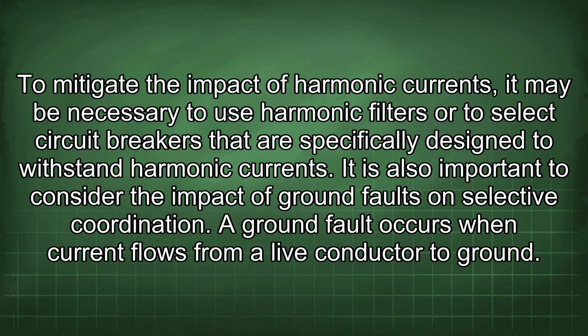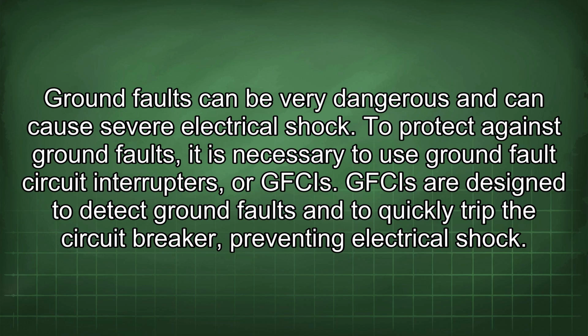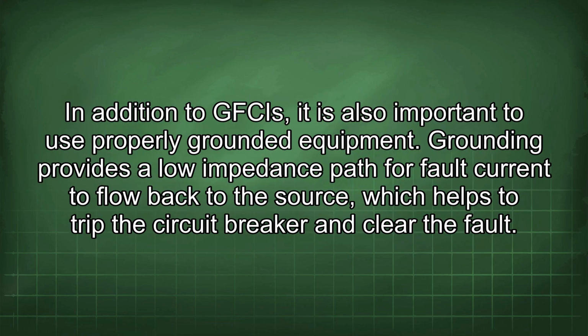It is also important to consider the impact of ground faults on selective coordination. A ground fault occurs when current flows from a live conductor to ground. Ground faults can be very dangerous and can cause severe electrical shock. To protect against ground faults, it is necessary to use ground fault circuit interrupters, or GFCIs. GFCIs are designed to detect ground faults and to quickly trip the circuit breaker, preventing electrical shock. In addition to GFCIs, it is also important to use properly grounded equipment. Grounding provides a low impedance path for fault current to flow back to the source, which helps to trip the circuit breaker and clear the fault.